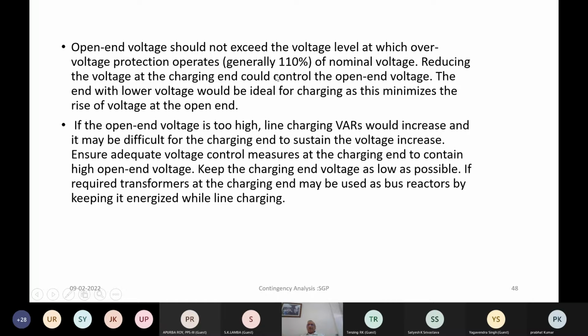Open end voltage should not exceed the voltage level for which the overvoltage protection operates. So it's necessary that overvoltage protections, which might generally be kept at 110, should be properly time coordinated. If required during black start mode, maybe the time delays could be suitably increased to permit, so the line should not trip on over voltage immediately after charging.